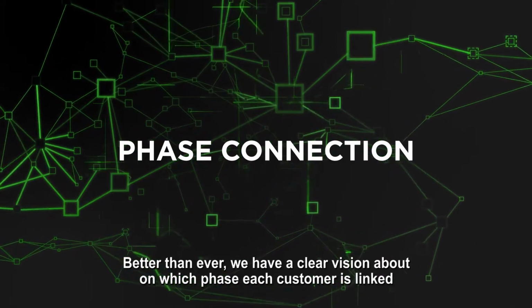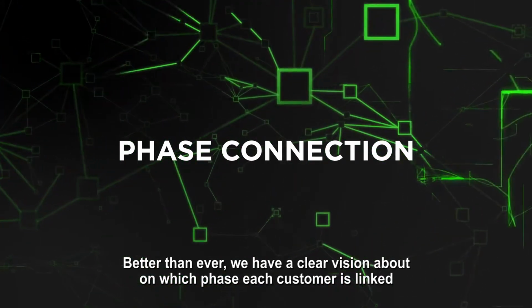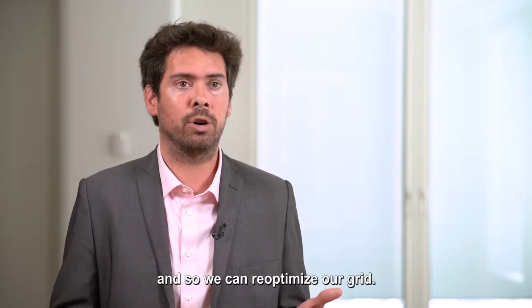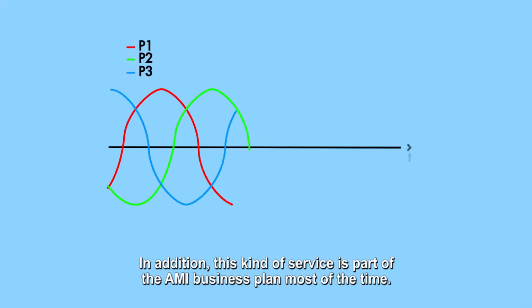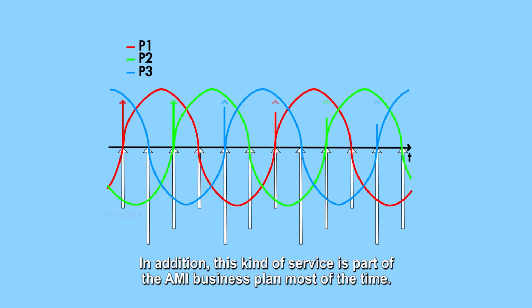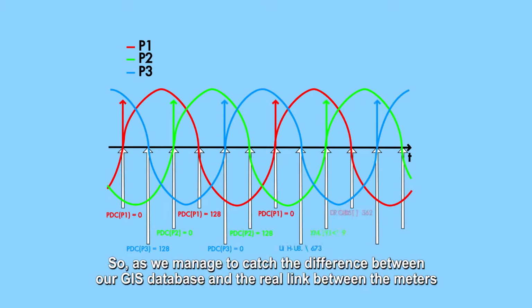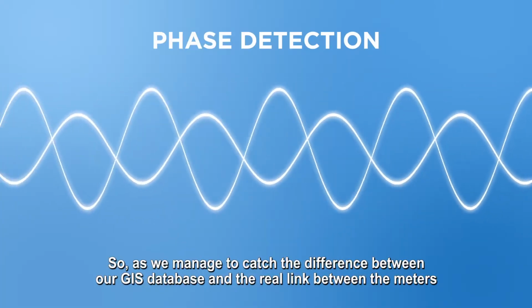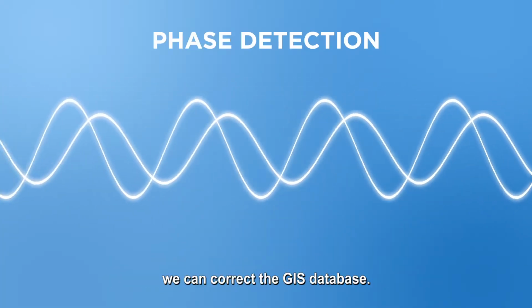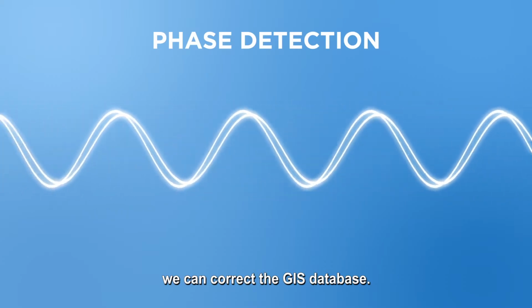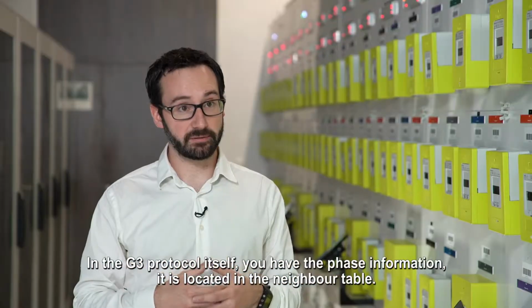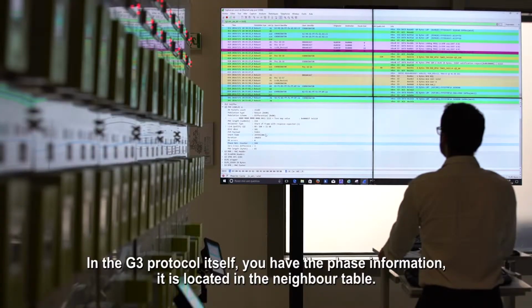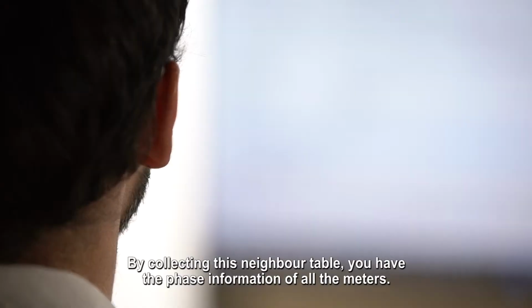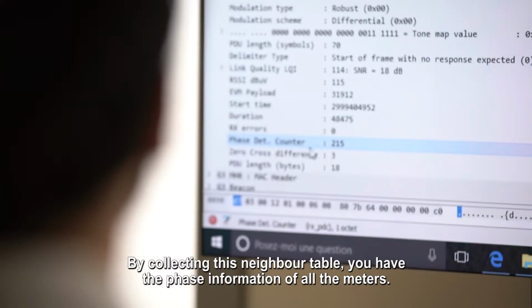Better than ever, we have a clear vision of which phase each customer is linked to, and so we can re-optimize our grid. In addition, this kind of service is part of the business plan most of the time. So as we manage to catch the difference between our GIS database and the real links between all the meters, we can correct the GIS database. In the G3 protocol itself, you have the phase information. It is located in the neighbor table. By collecting this neighbor table, you have the phase information of all your meters.